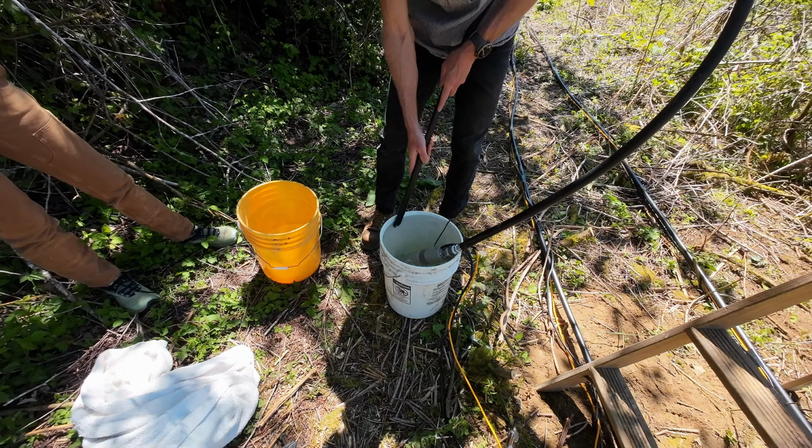And now we'll see that. Now this is the well sensor, so this should turn it off. It takes a minute for it to turn it off. There it goes. So this pump, because you don't want to twist the pump in the well, it speeds up and slows down slowly, so it doesn't torque anything. But we've got not a fault, but it just says well is low.